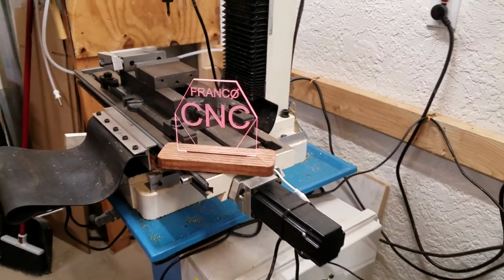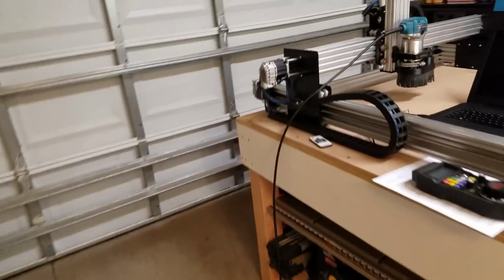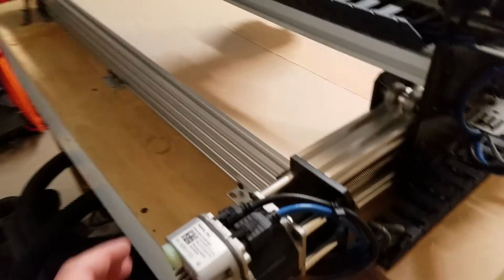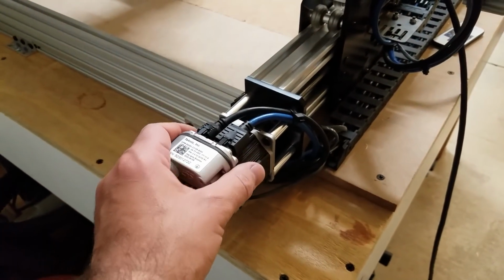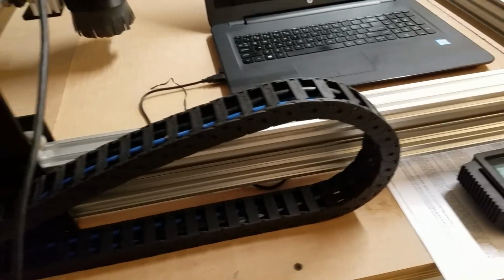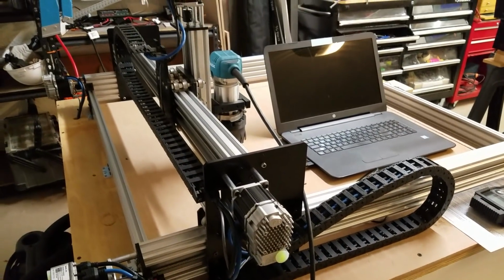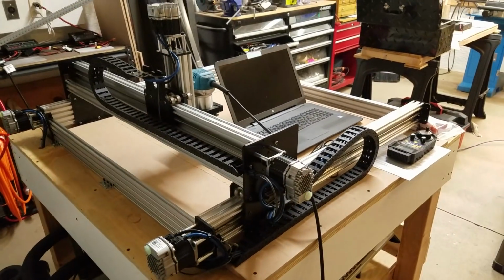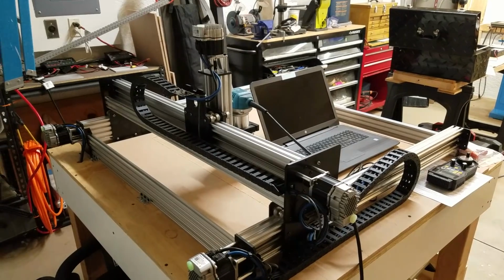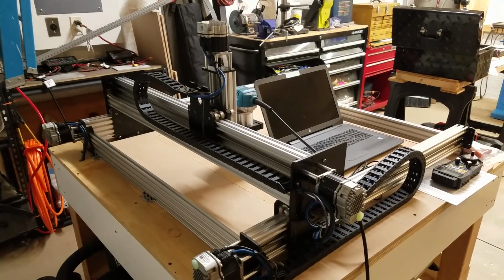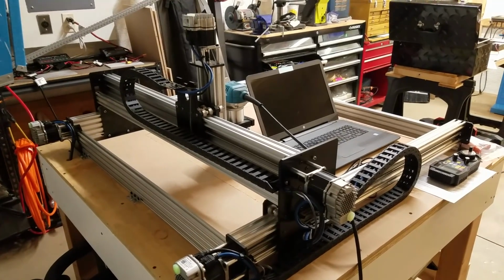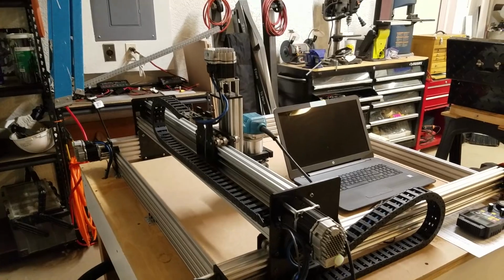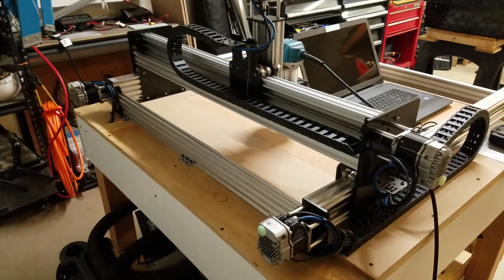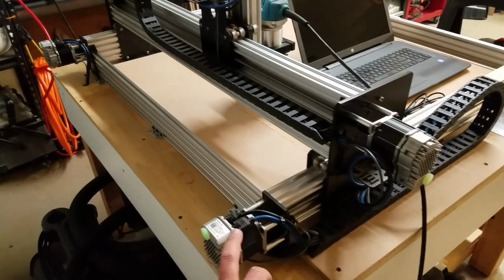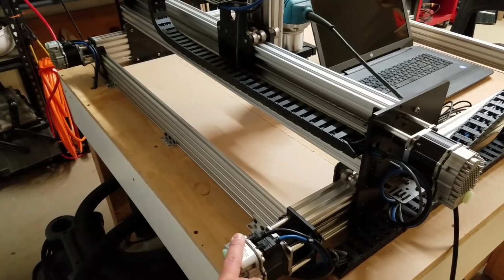So what I'm working on here tonight is part two of the Teknic ClearPath motor tuning procedure. In the previous video, the previous really long video, I'm sorry that other video was so long, I went through the whole process of doing the Z-axis and the X-axis. Even though the process definitely takes several minutes, it's actually pretty user-friendly, and you let the software do all the tuning for you. The trick with a gantry type of machine with a double y-axis is you cannot run each individual y-axis by itself to do the auto tune.